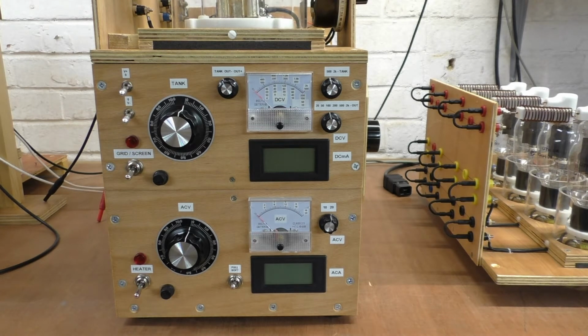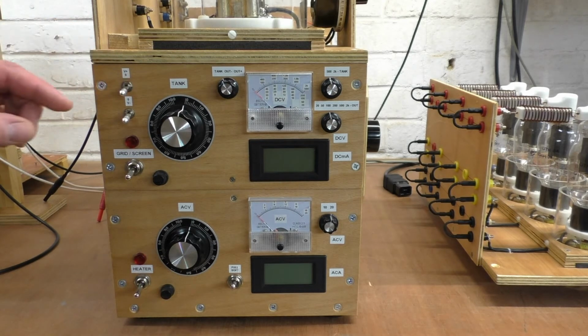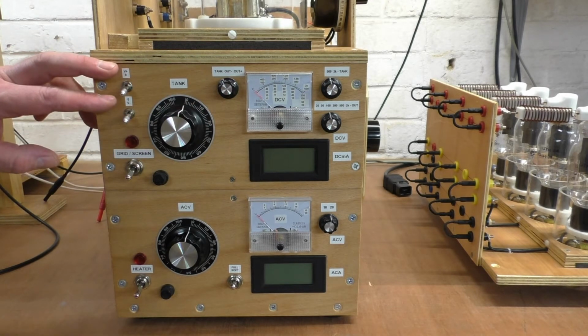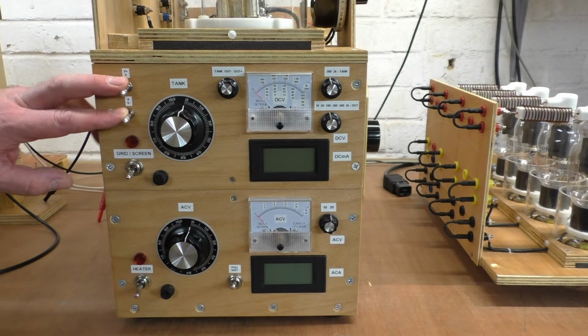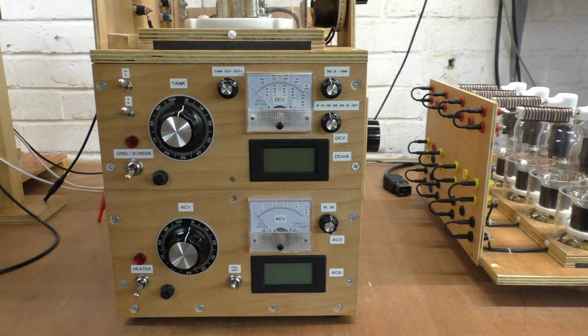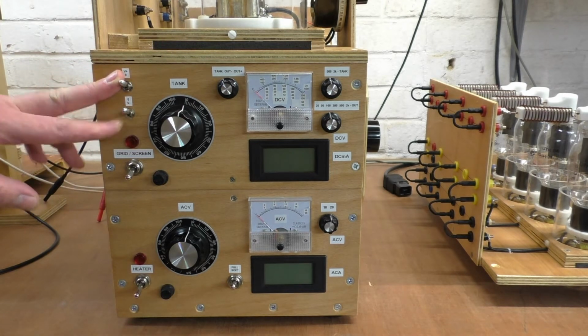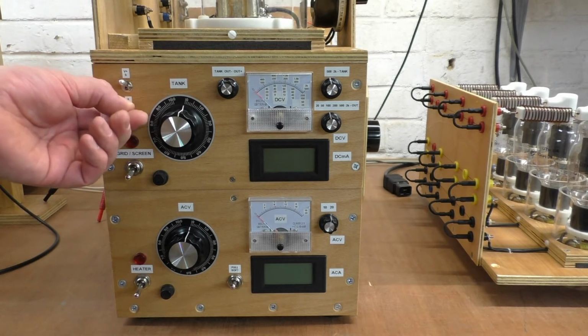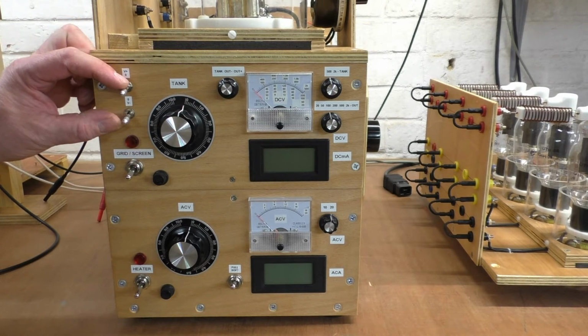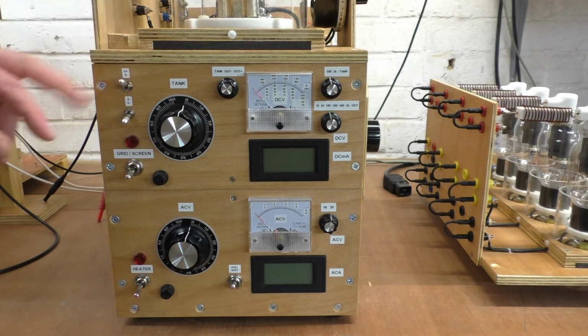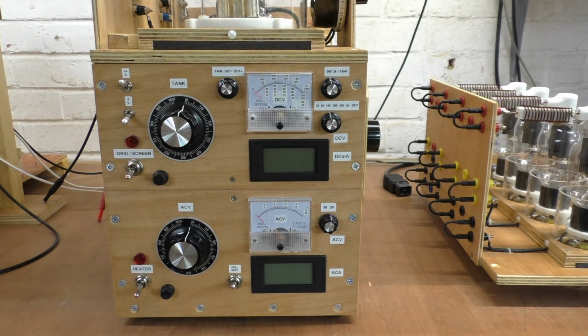We've also arranged it so that the bias output can be configured with these locked switches here. These are lock switches so they can't be moved, which is important, because if you were to move them you would start changing the bias positions. You can take the output of the rheostat from just the negative half of the centre tap transformer by flipping them up, or from just the positive part of the transformer. That would give you 0 to 700 volts at full tank. That, for example, would give you 0 to minus 700 volts. And if you want to work on positive and negative, you can flip them to positive and negative, so you are now across both secondary coils of the grid transformer. That allows you to configure how you want to run the output.